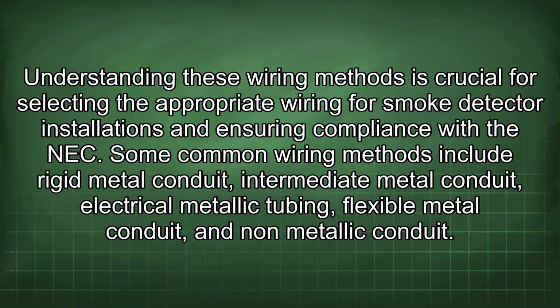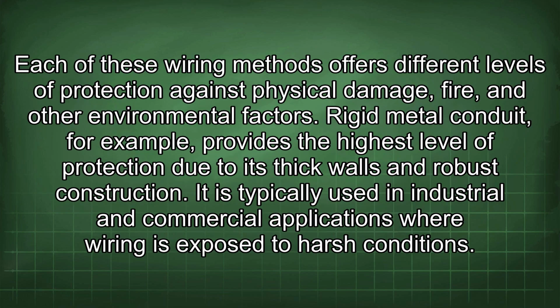compliance with the NEC. Some common wiring methods include rigid metal conduit, intermediate metal conduit, electrical metallic tubing, flexible metal conduit, and non-metallic conduit. Each of these wiring methods offers different levels of protection against physical damage, fire, and other environmental factors. Rigid metal conduit, for example, provides the highest level of protection due to its thick walls and robust construction. It is typically used in industrial and commercial applications where wiring is exposed to harsh conditions.